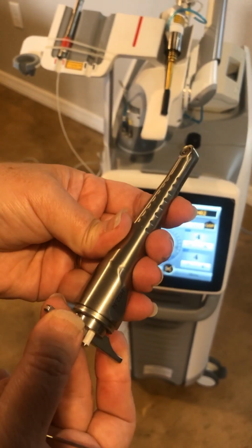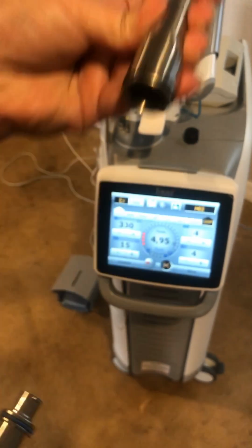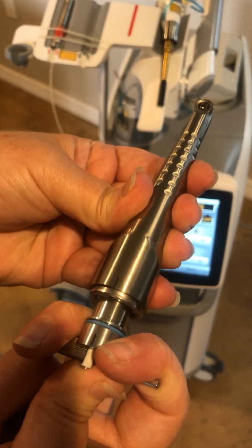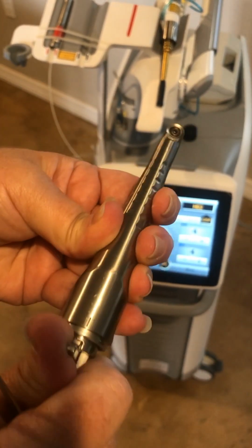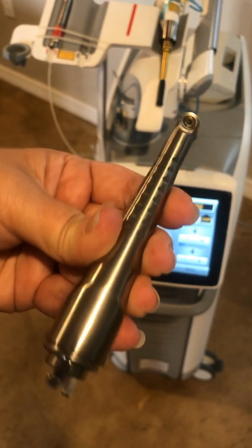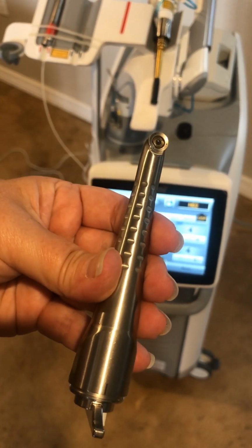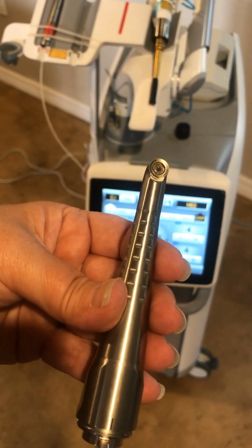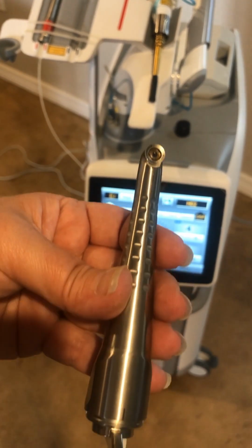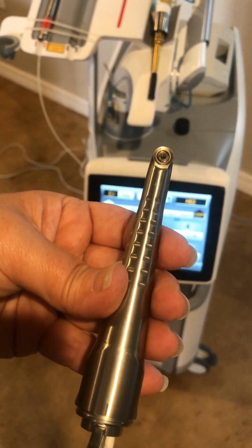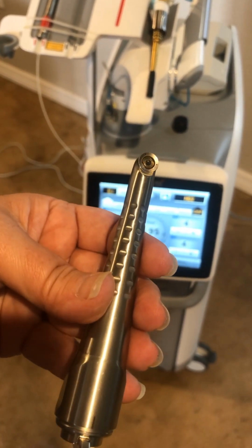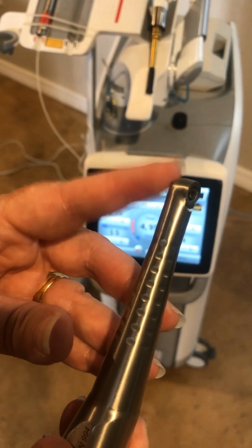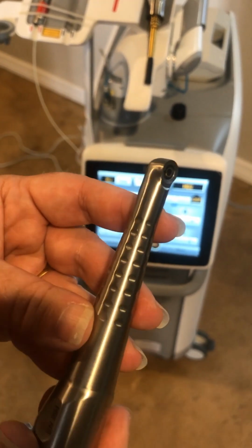So to take out the plug, you line the lines up together, pull straight out, okay? To put them back in, you line up the lines, push in, and turn, and then that's locked. Now it's properly ready to go through sterilization. Ideally, I would run this through your autoclave. The Statim is actually better for this, less damaging. But if you're running it through an autoclave, run it unbagged. When you run it with a bag, it has a tendency to push that water into that mirror area more.